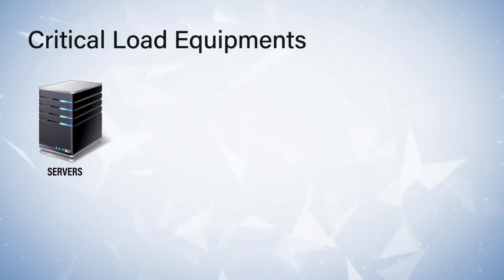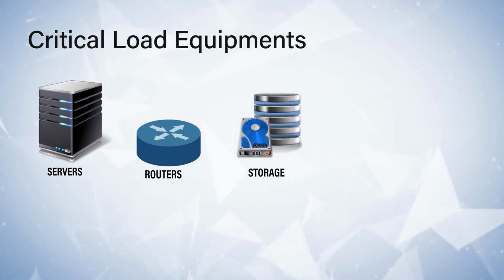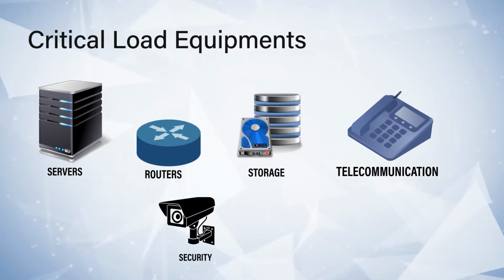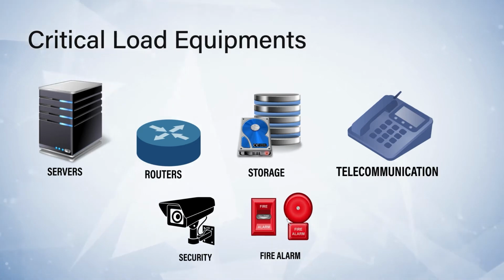The power used for servers, routers, storage devices, telecommunication equipment, security systems and fire monitoring systems, all of these form the critical load, because they are critical devices of our data center, and these devices need to be up all the time. Now, once you have made a list of the devices, first note down the power rating of these devices and their voltage requirement, whether it's single phase or three phase. We need to know this beforehand to design an efficient power system according to the equipment we have.